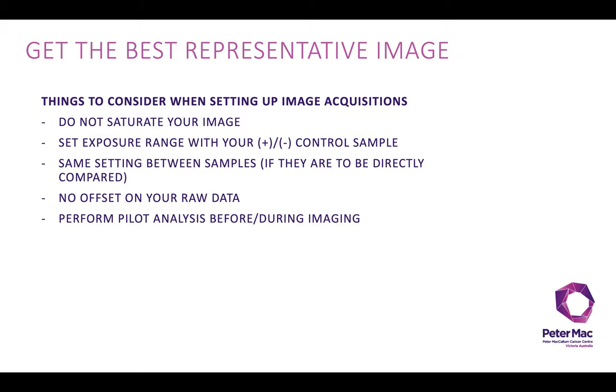Some other things to consider when setting up your image acquisitions: do not saturate your image — we'll cover that in the next few slides. Use positive and negative controls to set up your exposure settings. Use the same settings between samples if you want to directly compare them. Don't use the offset, and perform a pilot analysis.